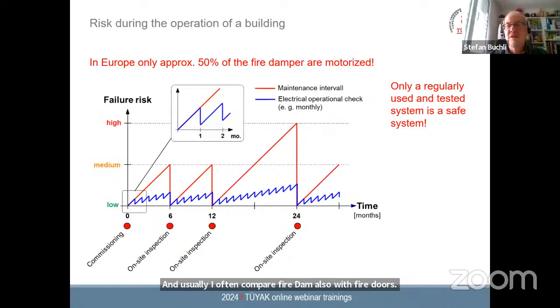The fire doors have one big advantage. You walk through the door several times a day, and each time you walk through the door, you open it, it closes. It's like a test. So you use it on a regular basis, and you can be quite sure that the door is working in case of a fire. And if it's not working, hopefully the guy walking through the door realizes, oh, the door is not closing correctly. I report this to the facility manager. Unfortunately, the fire damper has the same function as the door, but it's not visible because the fire damper is hidden somewhere under the ceiling, but has the same functionality.